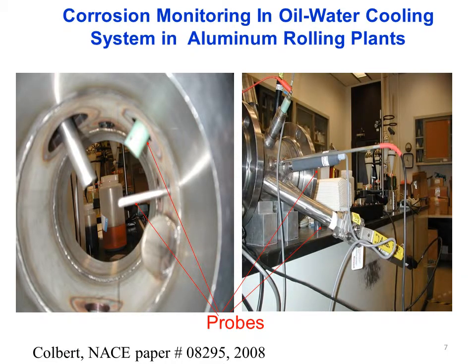This slide depicts corrosion monitoring in oil-water cooling systems in aluminum rolling plants. This image depicts the interior of a piping structure and the orientation of the CMAS probe. CMAS probe can be manufactured to a variety of insertion depths, such that the probe can be either flush with the pipe wall or can be intruding into the inner area of the pipe.